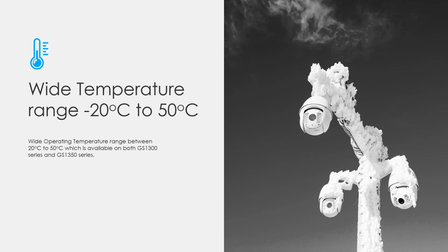All of these switches have a wider temperature range, so you can install them not in outdoor environments, but in waterproof cabinets that are outdoor but not heated, for example, parking garages or electrical cabinets or whatever. And this doesn't mean that these are outdoor switches, as said, so you still need some water protection, etc. But the temperature range is there.